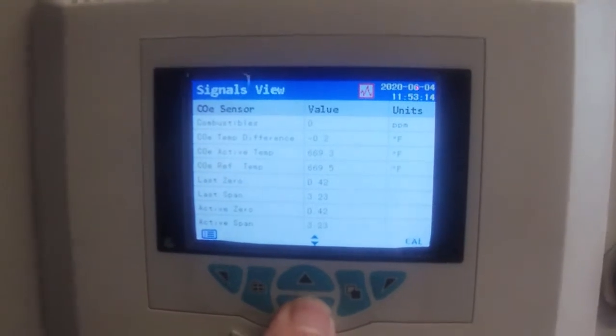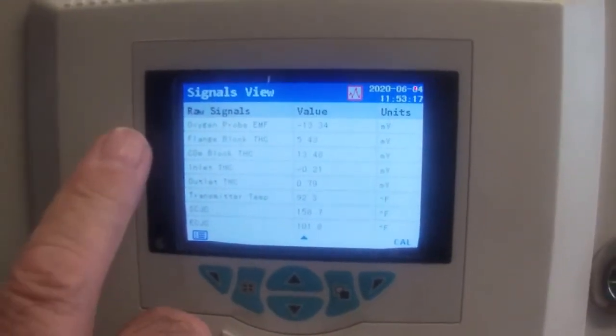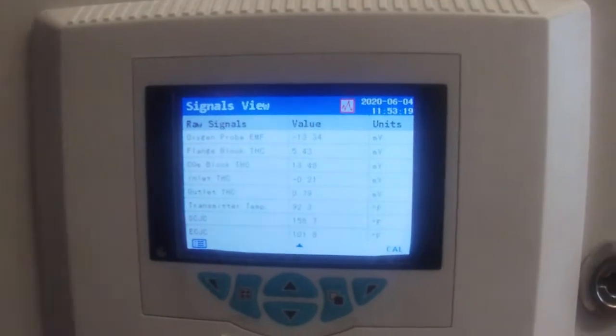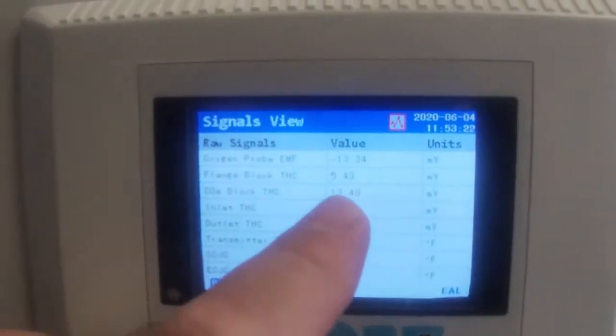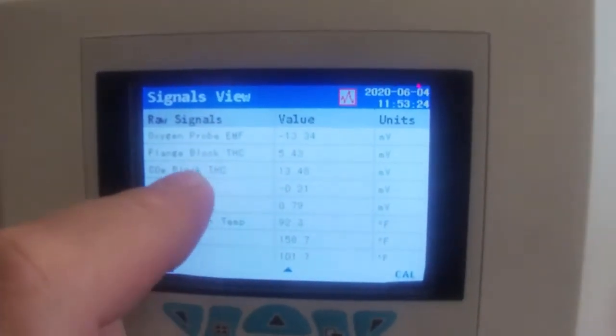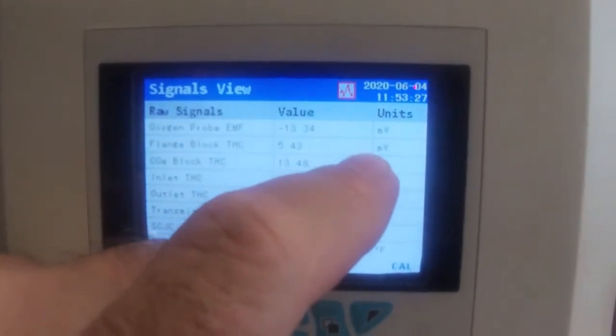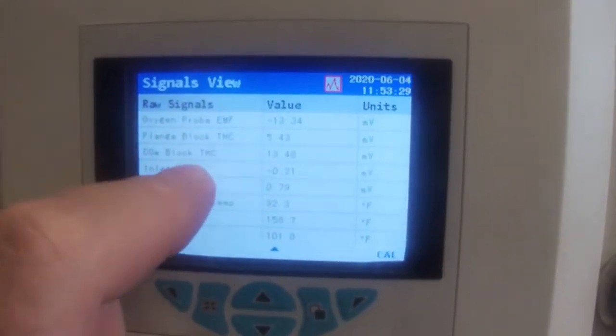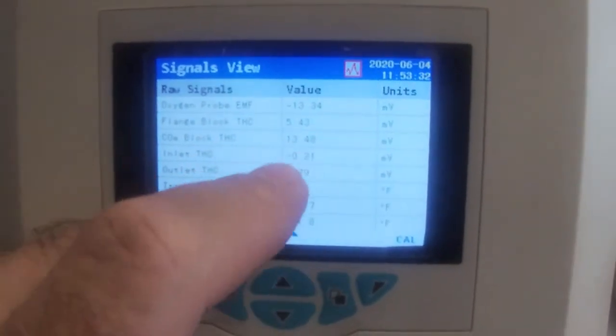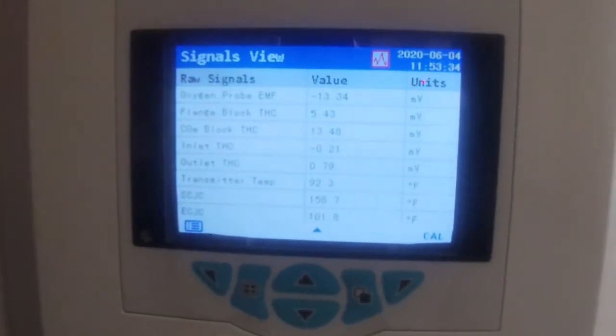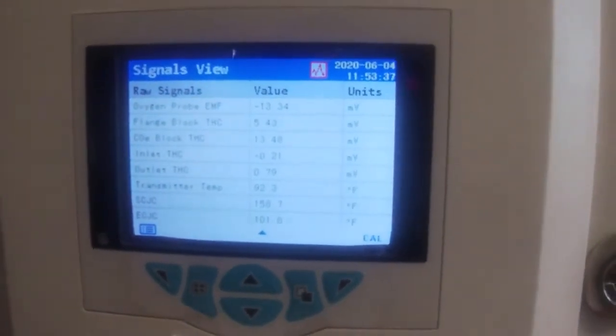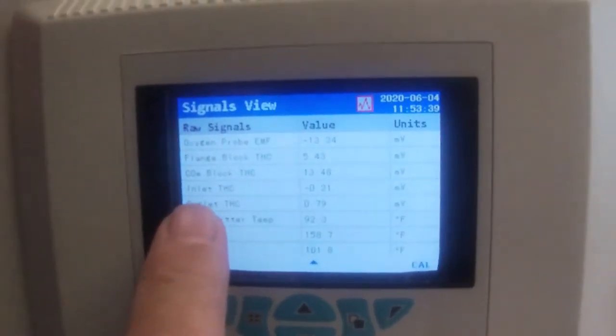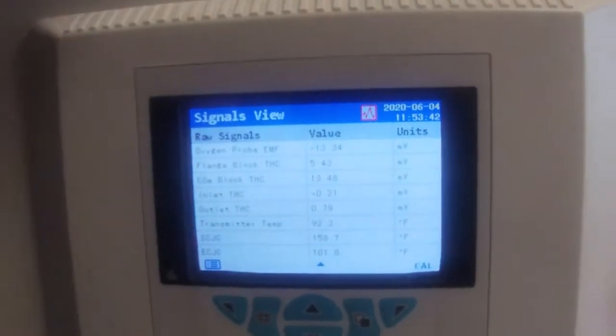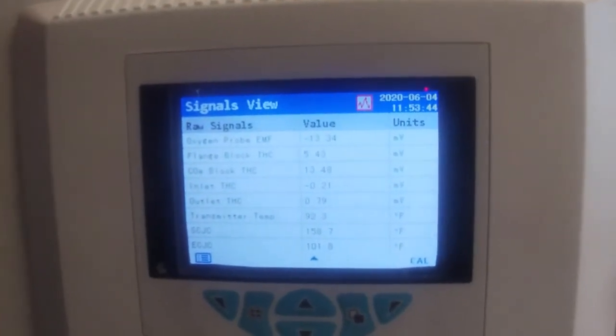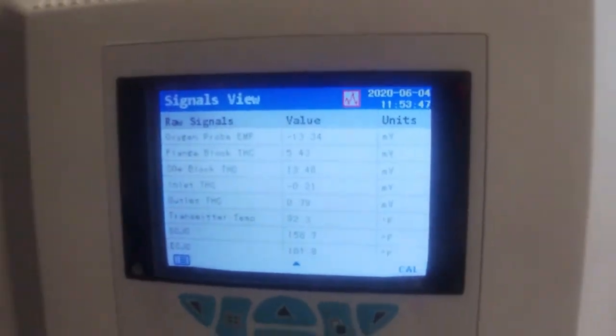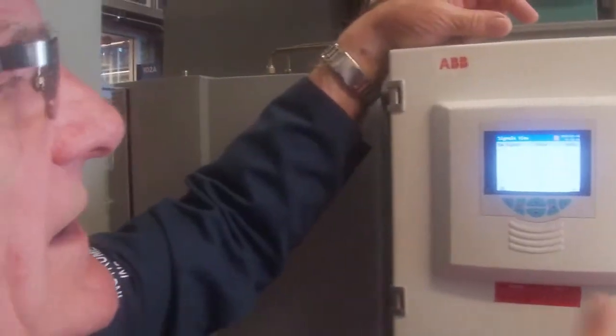If I go down to the next page, this is showing the raw signals coming in. So how many millivolts is coming from the oxygen probe? The flange block, number of millivolts coming off a thermocouple there. COE block, number of millivolts coming off of that one. So if you want to calculate it yourself using your thermocouple tables, you could. Inlet and outlet thermocouples, those are the two that I showed you up there before, the type K thermocouples, which are measuring the air temperature coming into the boiler and the flue gas going out of the boiler.